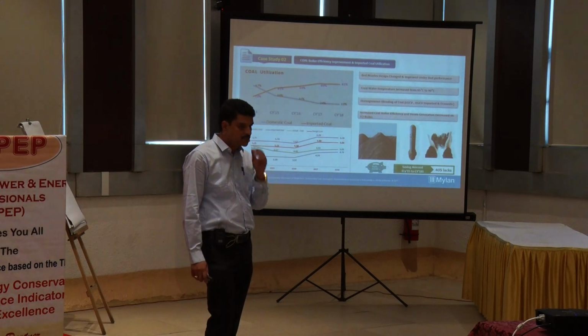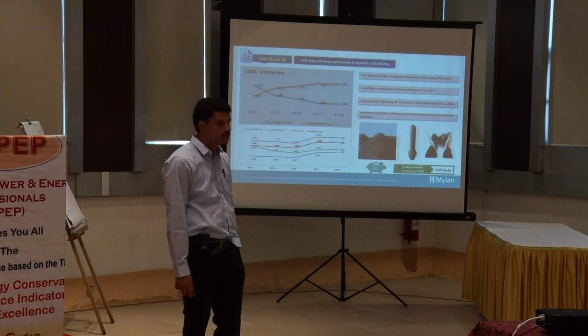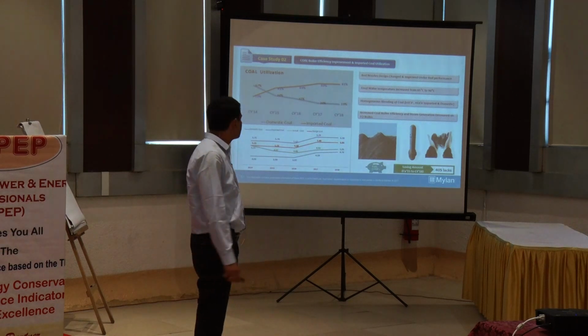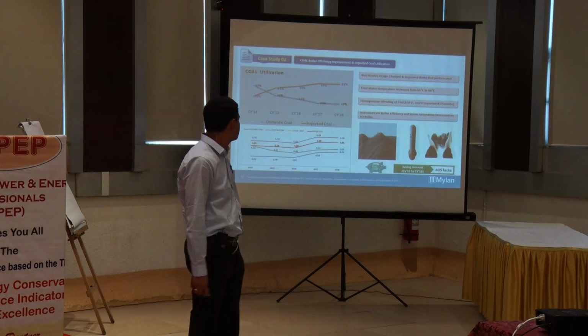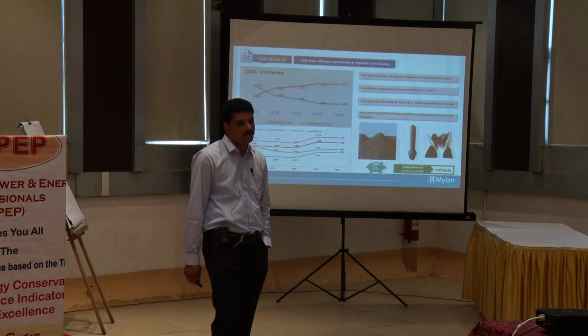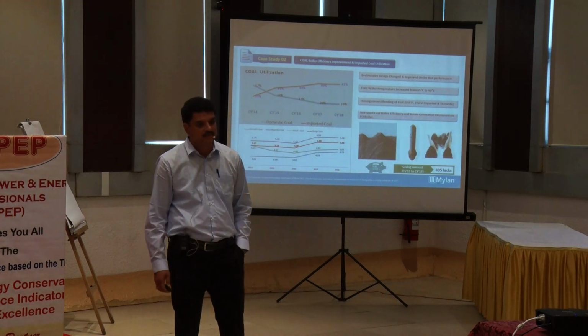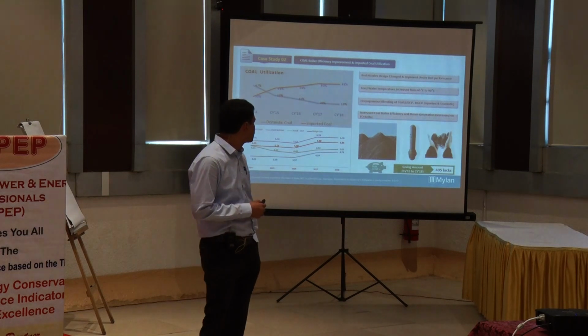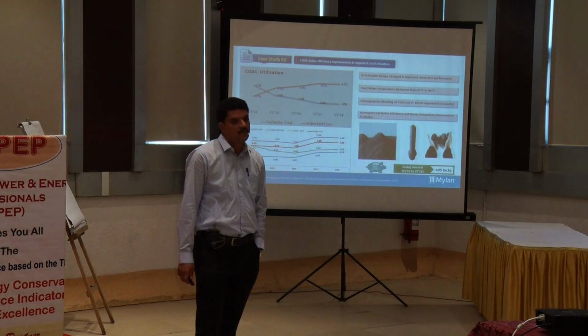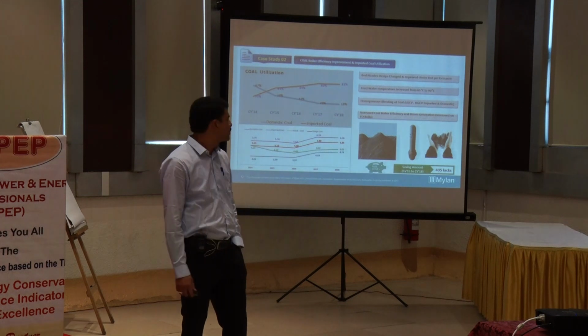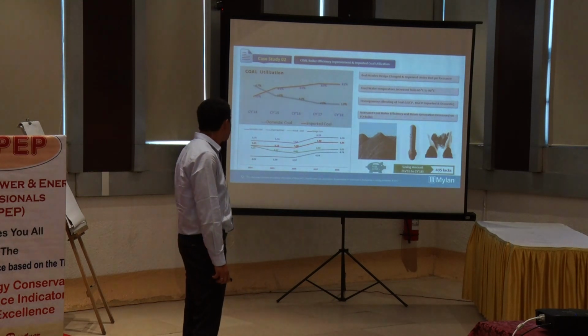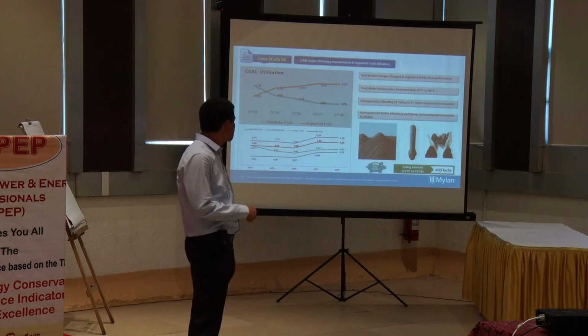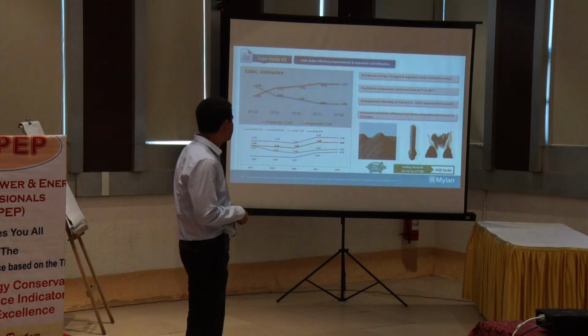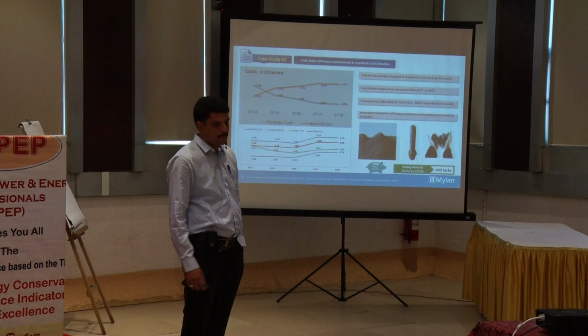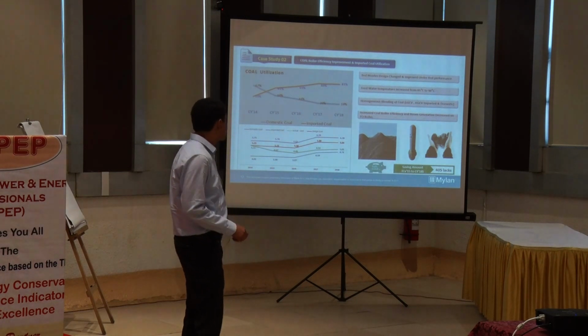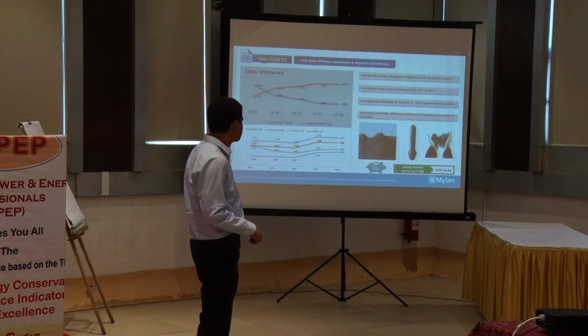This is the coal price reduction. Our boiler is designed for utilization of domestic coal, and it can handle 30% of fines. So now we have modified our bed nozzle design, and we have implemented imported coal, and now we are using 80% of imported coal and 20% domestic coal. So with that, our coal procurement average cost reduced from 5.84 to 5.05 rupees. These are the savings achieved, sir. For 4 years, 405 lakhs savings achieved.